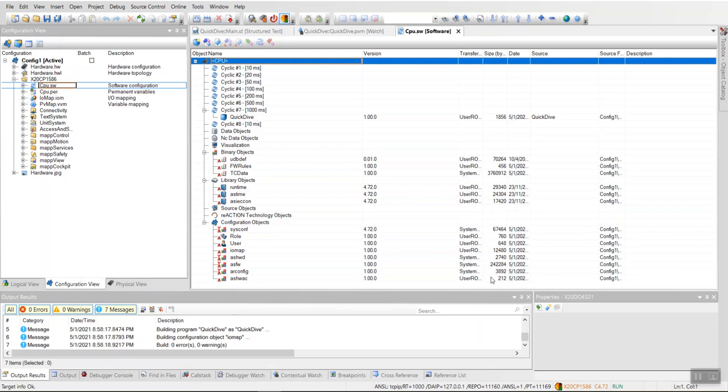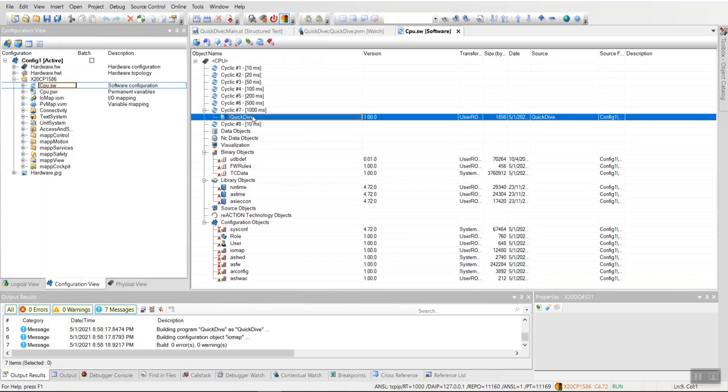So this is also an important thing to take note of when you're using Automation Studio, because this allows you an immense amount of flexibility in how you want to design your program. Say, for example, you have a sensor on the assembly line in school or in the factory, and you don't need your sensor to run at such a high frequency. So you don't need to monitor the output of the sensor so frequently. You can just put a program at 500 milliseconds or so. And let's say you have a program that needs to be executed with a high frequency. You can put it in cyclic task class 1.